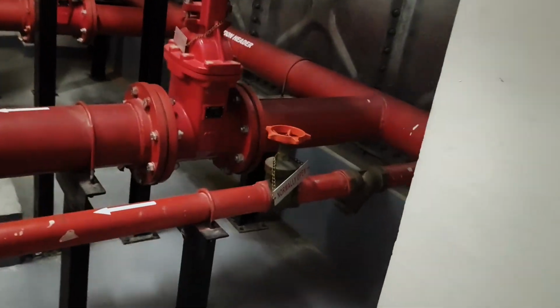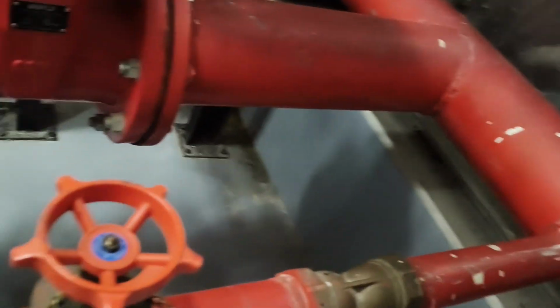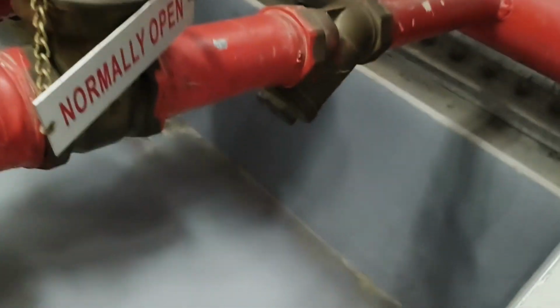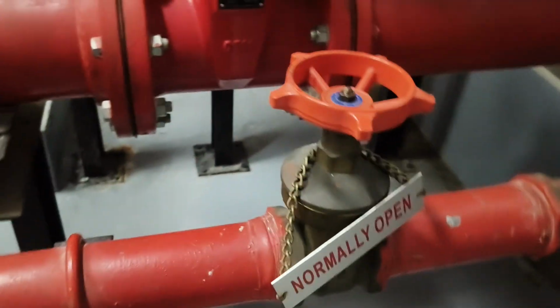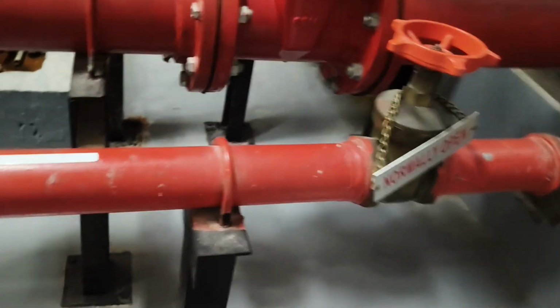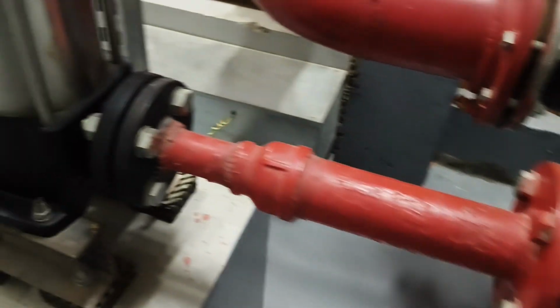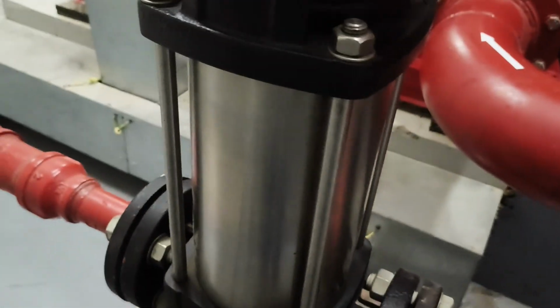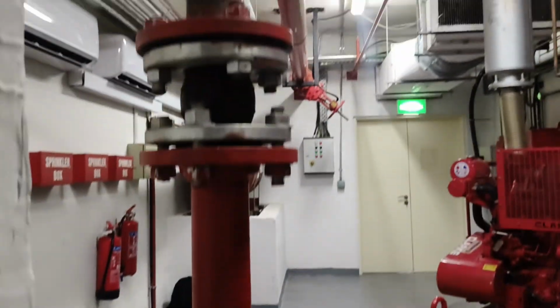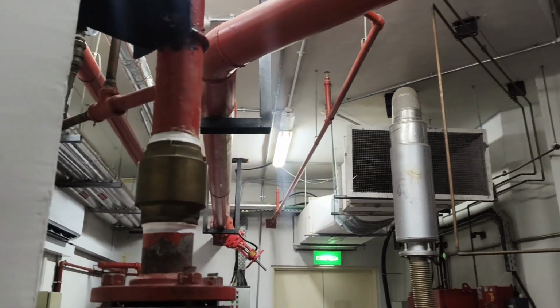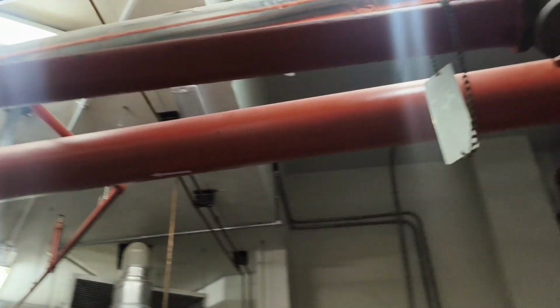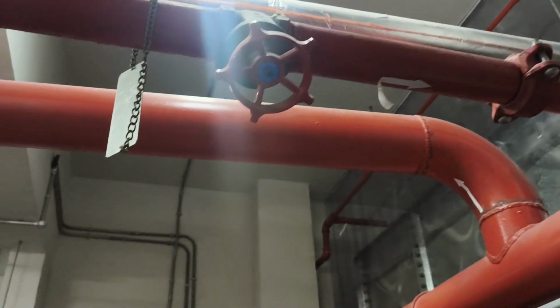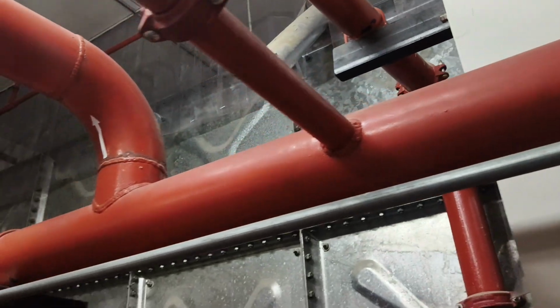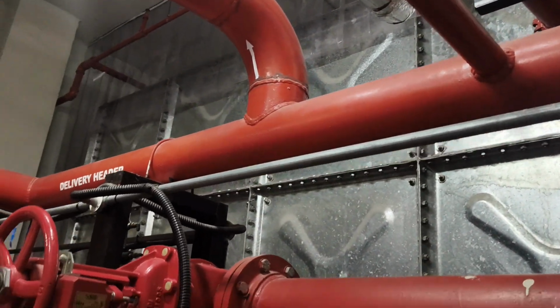From here you can see water is supplied directly, and the jockey pump has a strainer, then a gate valve which is normally open. From there it comes to the suction part of the pump, and the pump pumps it through the check valve to the sensing line, and through another gate valve to the delivery header.